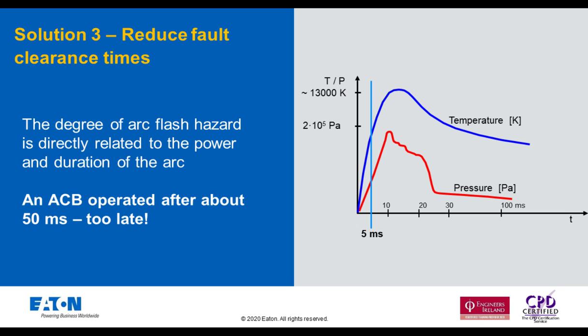Hence why the classifications of assemblies A, B, C and I, when tested in accordance with 61641, have been introduced. However, this is just a passive way of trying to mitigate the risks to personnel. There are some active means of arc reduction. We can see this via reducing the arc duration time.